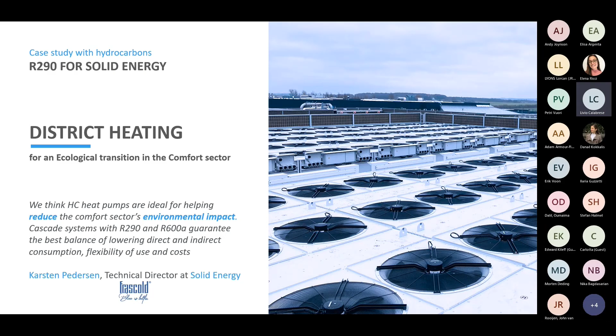Originally, heat in this district heating system came from wood chips, heat pumps, and a gas boiler, with a heating production of 45,000 megawatt hours annually. In 2019, Galten installed a 3.5 megawatt air-to-water heat pump using 6 screw compressors, the largest size.